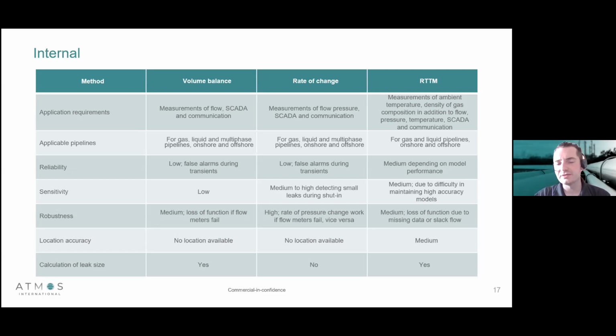The sensitivity of these two methods is relatively low, though on rate of change this can be slightly improved in static conditions or shut-in conditions when there's less noise in the pipeline. Robustness, they're both very, very good at that, but unfortunately they don't offer very good leak location accuracy.